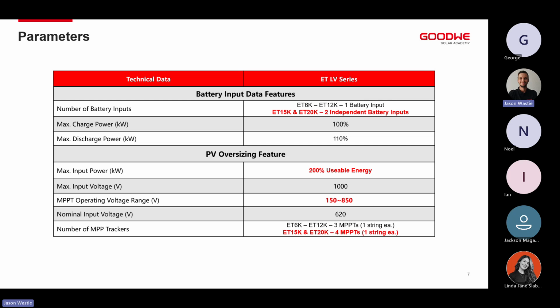And if we take, let's call it 10 minutes at a maximum over a 10-year span that the inverter is under warranty, or when doing a proposal, 10 years, 10 minutes extra every single day, it gives you a much higher PV generation outlook if you look at it overall over the duration or lifetime of the system. So as a sales perspective, it makes a massive difference. From an installation perspective, it could mean you could string your system at one less panel. Obviously, you don't want to go too low. However, if we get as close to that 620 volts as a nominal input, it will be perfect.